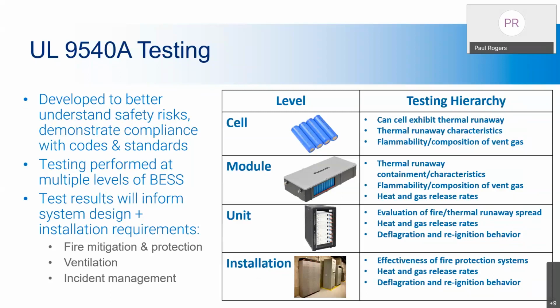We'd also look at deflagration, which for those who don't know means an explosion. If these things off-gas and that gas continues to build up, we could have a deflagration. But NFPA 855 and the IFC 2021 code addressed that by introducing deflagration venting or deflagration prevention, to actually mitigate or manage the deflagration through venting holes.